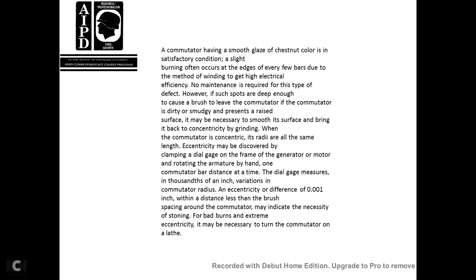if the commutator is dirty and smudged and presents a raised surface, it may be necessary to smooth the surface and bring it to concentricity by grinding. When the commutator is concentric, the radii are all the same length. Eccentricity may be discovered by clamping the dial gauge on the frame of the generator or the motor, rotating the armature one commutator bar distance at a time.